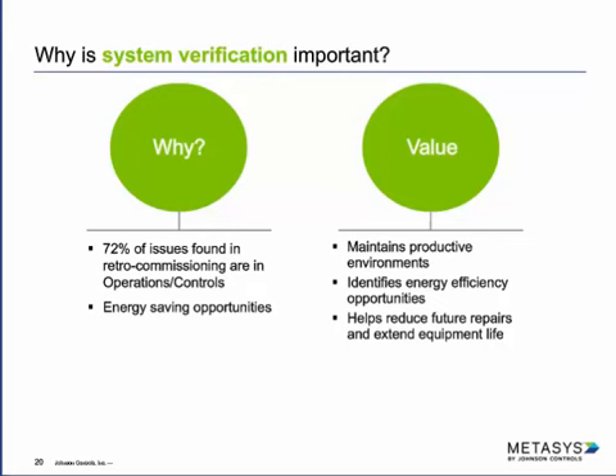Having had the privilege of working with Dr. Katipamula, often you kill two birds with one stone: you're correcting an energy efficiency issue, but you're also improving control of the environment, whether that's occupant comfort or the precise control needed for a data center or manufacturing operation. Finally, a lot of these issues can cause excessive cycling, which causes wear and tear on the physical equipment. So by addressing control issues, you often get a positive benefit to your mechanical equipment running more efficiently.